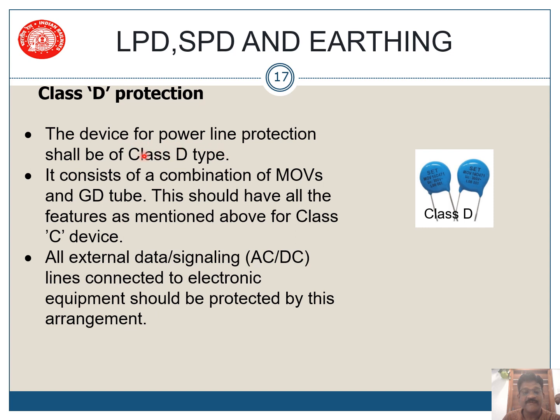The device power line protection shall be of class D. It consists of a combination of metal oxide varistors and gas tubes. This should have all the features as mentioned above for class C also. All external data or signaling lines connected to electronic equipment should be protected by this arrangement. This is also available, you can see, in LED signals. But generally we should be very careful. If this gets short circuited, your UCR can pick up even when your bulb is not glowing, because this may have become defective. Remove them in such case.